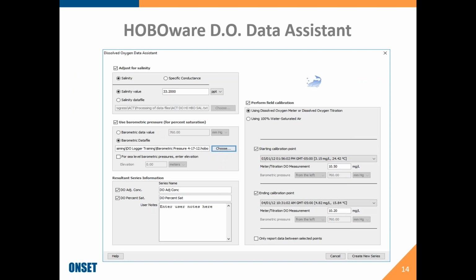This is an example screenshot from the dissolved oxygen data assistant. It gives you the ability to calculate salinity adjusted DO, and you can use the field calibration to adjust for special conditions or compensate for fouling again. It's very simple - just enter the data in the specified fields and get your end result.